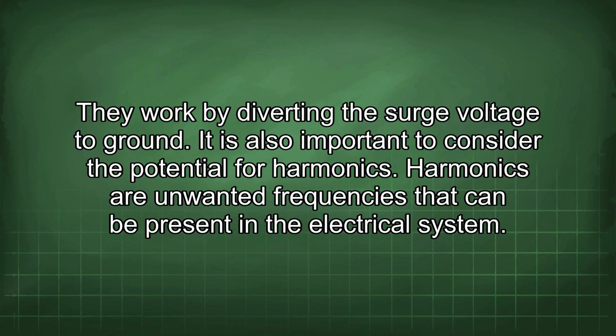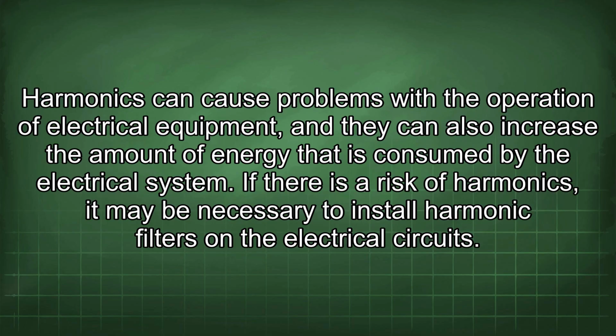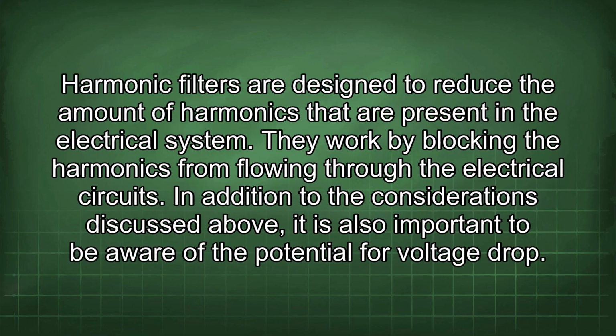It is also important to consider the potential for harmonics. Harmonics are unwanted frequencies that can be present in the electrical system. Harmonics can cause problems with the operation of electrical equipment, and they can also increase the amount of energy that is consumed by the electrical system. If there is a risk of harmonics, it may be necessary to install harmonic filters on the electrical circuits. Harmonic filters are designed to reduce the amount of harmonics that are present in the electrical system. They work by blocking the harmonics from flowing through the electrical circuits.